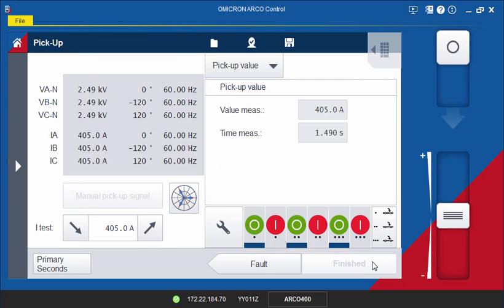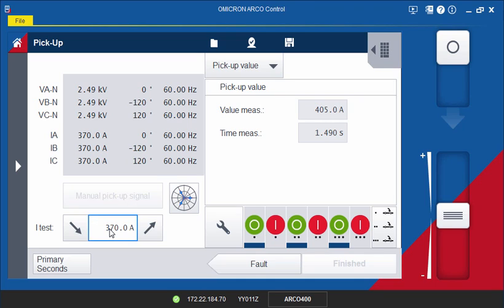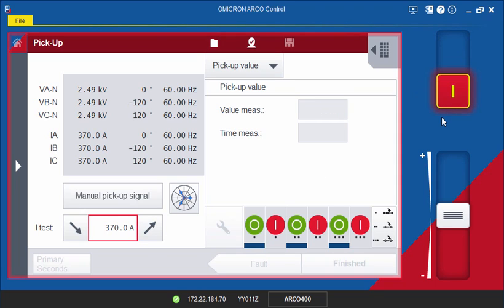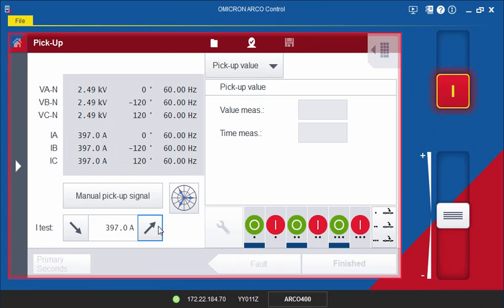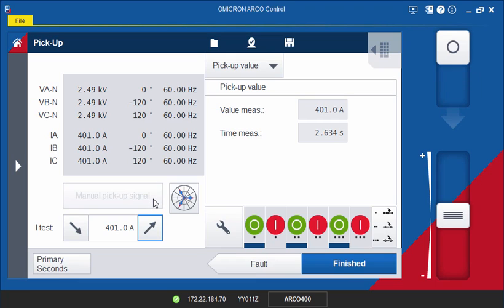Enter the starting value for your ramp. Make sure that this value is below the minimum pickup value of the overcurrent elements you are testing. Then, activate the outputs and click the Up arrow to increase the output values. The rate of increase is automatically calculated by the ARCO Control software. As soon as the controller picks up, stop the test by clicking the Manual Pickup Signal button. You can then analyze your results and add them to your report.